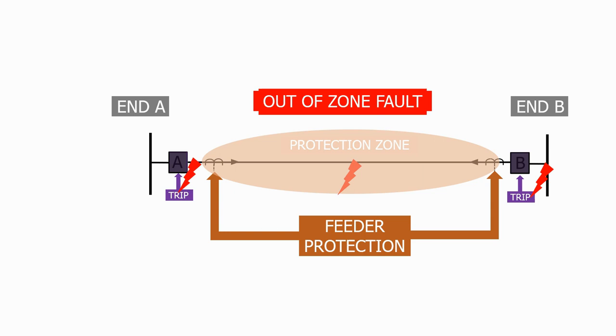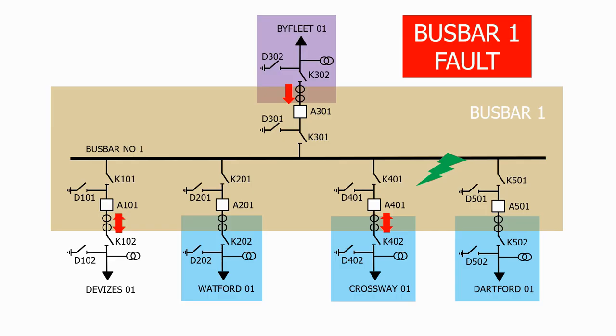Many of the protection systems that we use on the transmission network use defined zones to work out where the fault is on the network and operate the correct circuit breakers to clear it from the system. We will look at how these protection zones are defined and how we position the current transformers correctly to define the zones that we require.